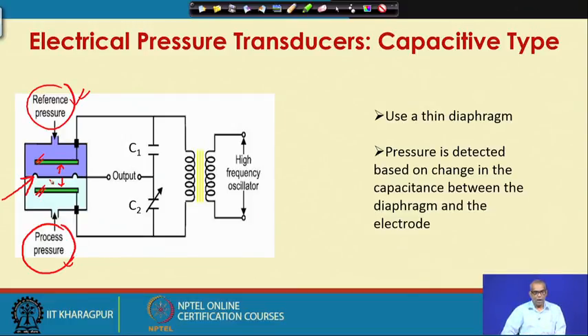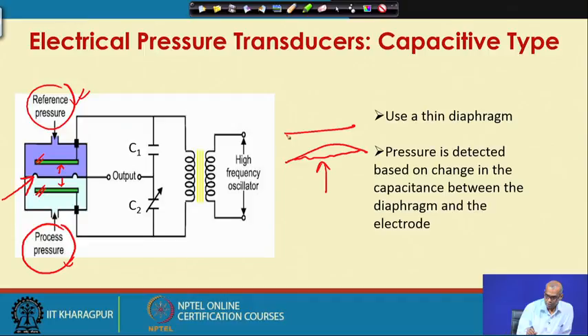So, the capacitive type electrical pressure transducer uses a thin diaphragm. You apply pressures, then the pressure is detected based on change in the capacitance between the diaphragm and the electrode. If you use only one pressure source, what I can do is keep one electrode fixed and one diaphragm which will change its position. So, one electrode fixed and another diaphragm, let us say this is the diaphragm. With application of pressure, this diaphragm will change position. So, the capacitance between this electrode and this diaphragm will change. So, the displacement can be converted to an electrical signal.